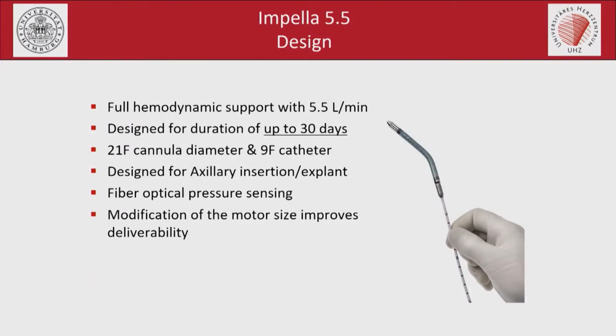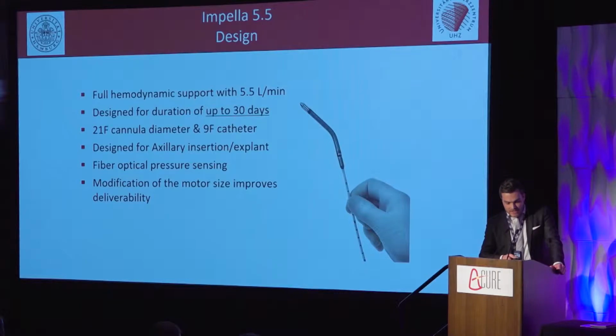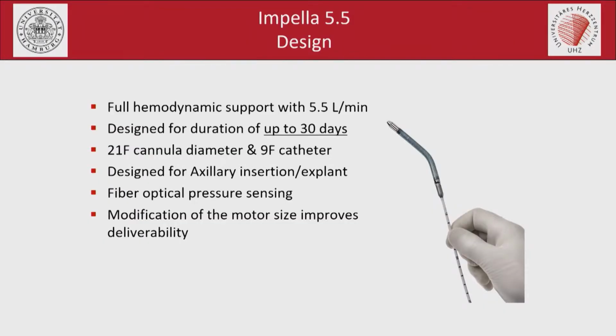So the Impella 5.5 provides hemodynamic support up to 5.5 or even 5.8 liters, depending on the afterload, and it's designed for a duration up to 30 days. Again, it's a 21 French cannula mounted on a 9 French catheter. It's designed for only axillary implantation. In contrast to the 5.0, it has a fiber optical pressure sensing. And the modification, the lack of the pigtail catheter, and I will show you some fluoroscopy images, improves the deliverability of the pump.